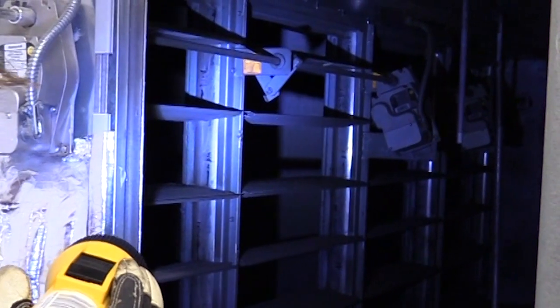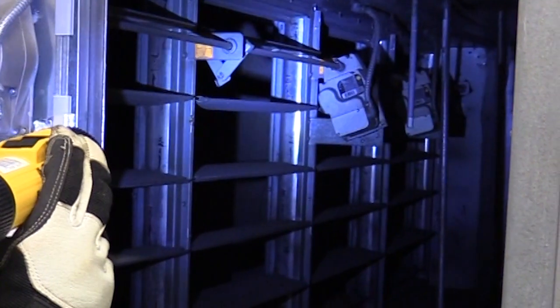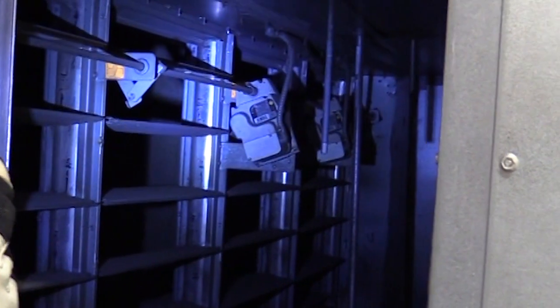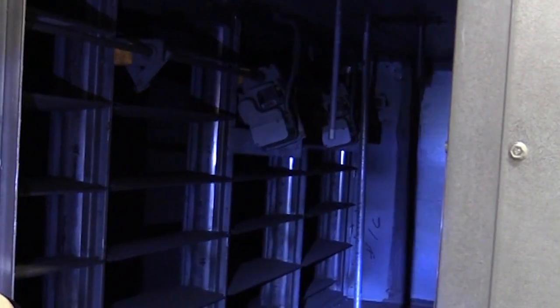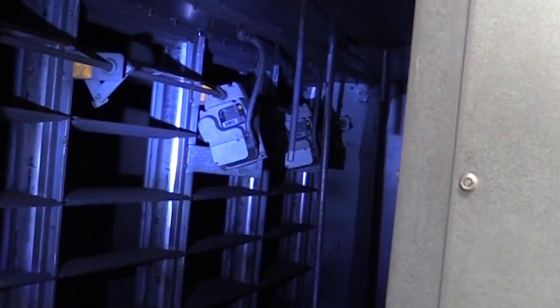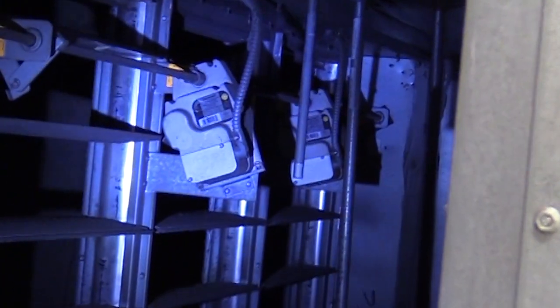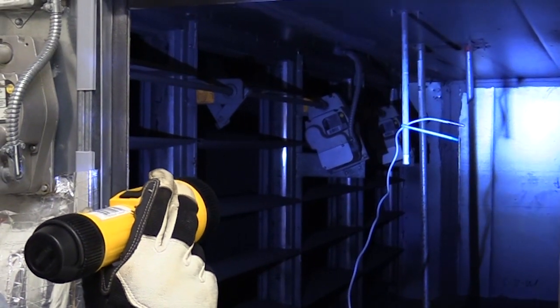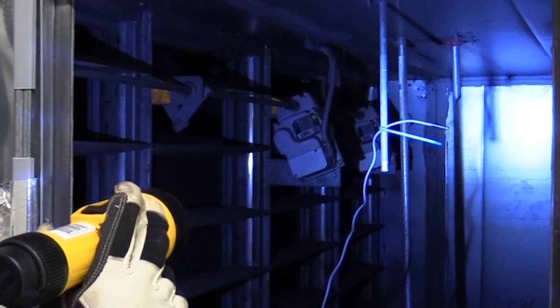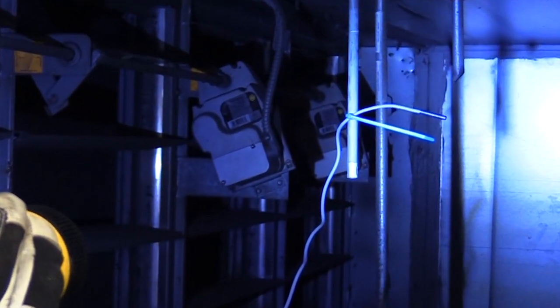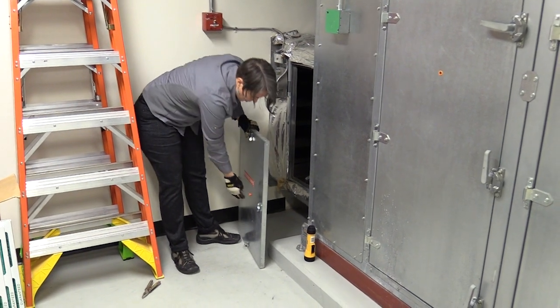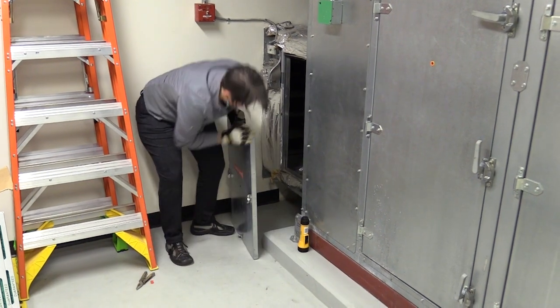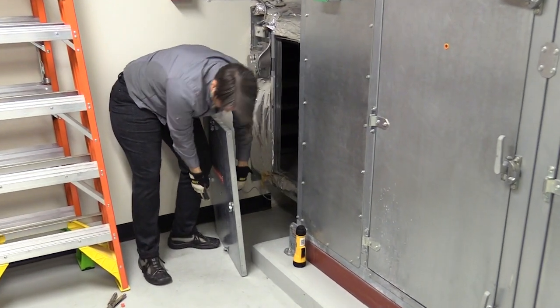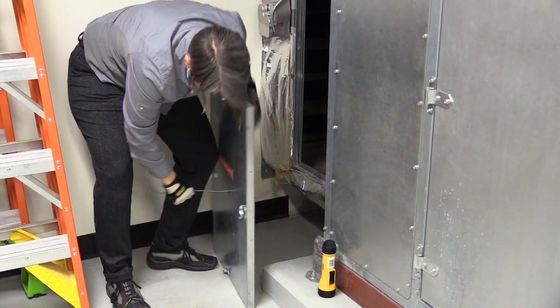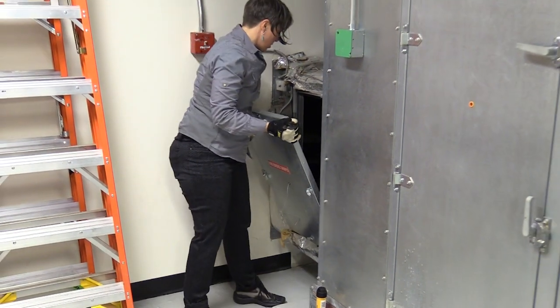You can see the outside air damper wide open currently. You can see the actuator for the damper and the linkage. So when troubleshooting an issue that may come up, you always want to check and make sure the actual mechanical system is working properly. The linkage and the actuator are physically opening the damper. So you can see here I've secured the sensor in a position to where it's not going to touch any other surfaces and will stay secure for the duration of the logging period. So I've got this handy test port already installed in the door. So I'm going to just remove the test port cover, feed that sensor cable through, and replace the access door.